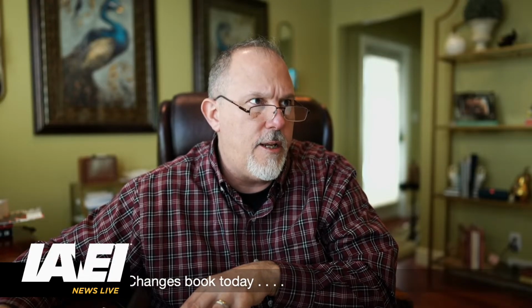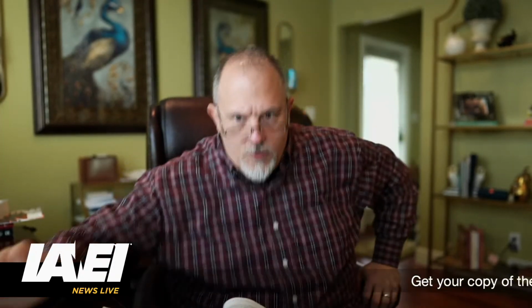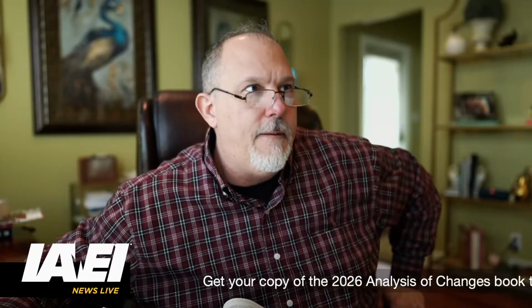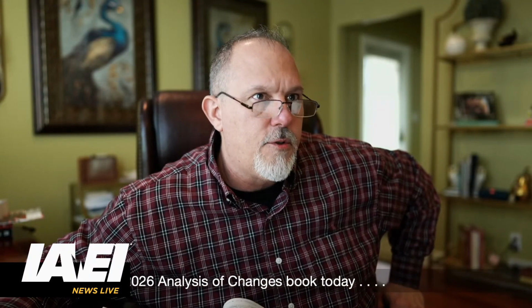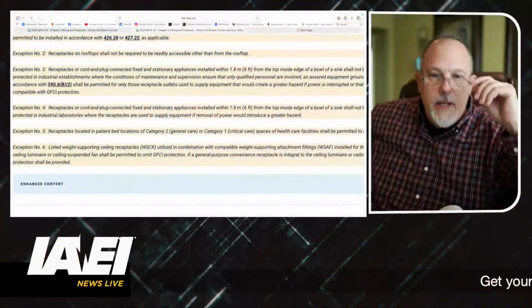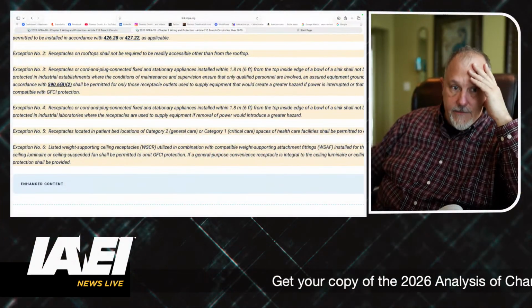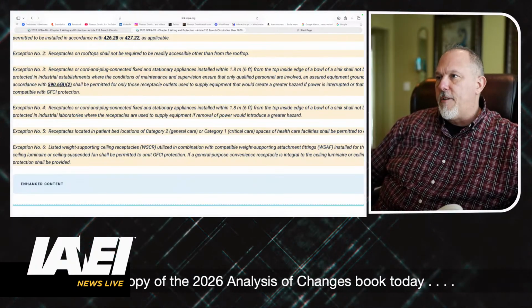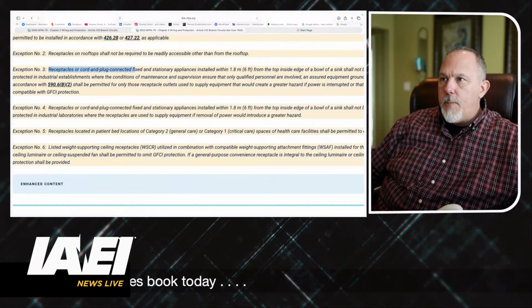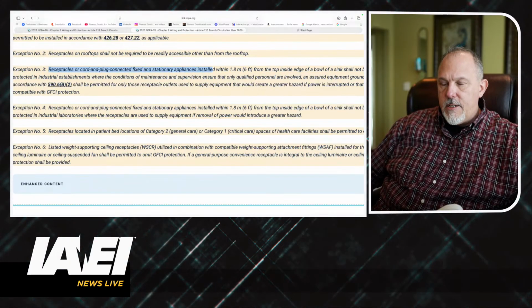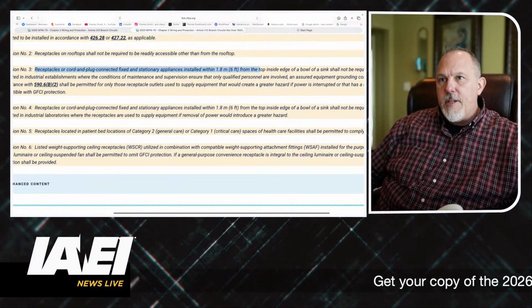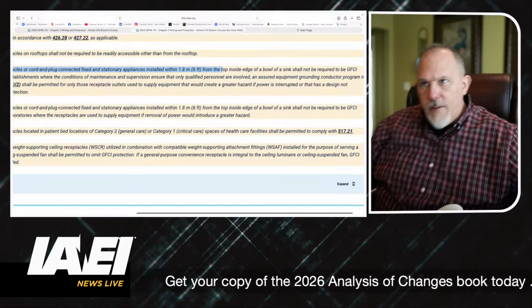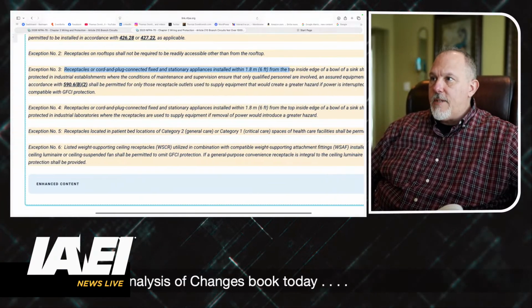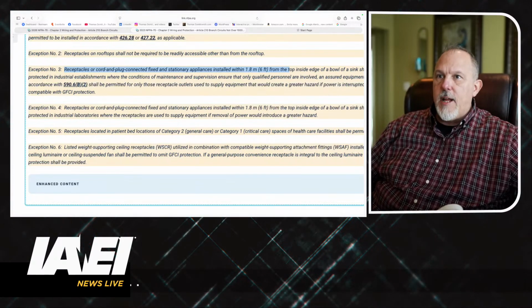So the big change in B, other than dwelling units, is the industrial exception number 2. Okay. I'm going to show you exception number 2, and I'll show you the problem that we had. So if you look at exception number 2, we say, I'm sorry, it was exception number 3. It said receptacles or cord and plug connected fixed and stationary appliances installed within 6 foot of the top inside edge of a bowl of a sink shall not be required to be GFCI protected in industrial establishments, blah, blah, blah.